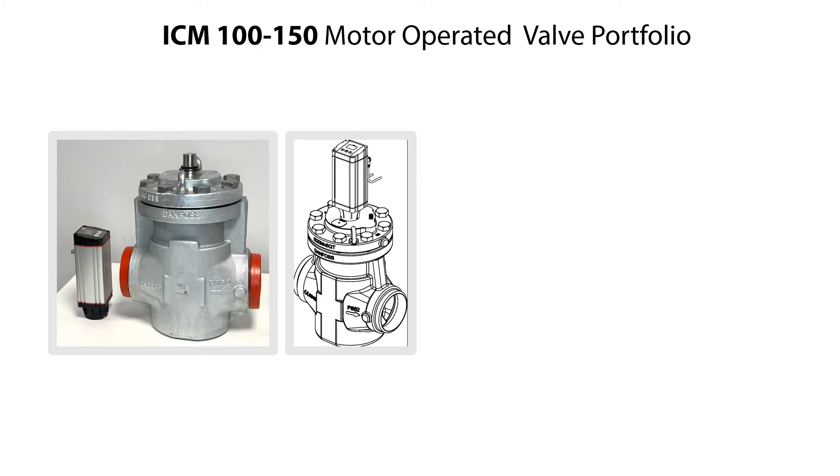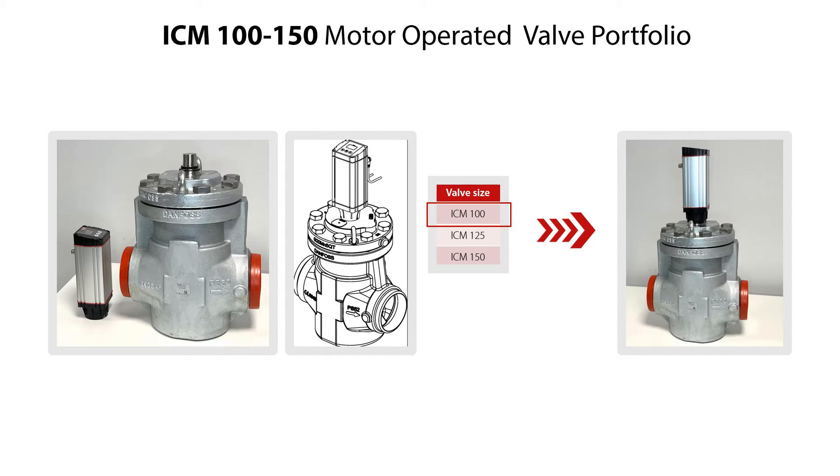The complete ICM 100-150 motor operated valves consist of a valve body with function module and ICAD actuator as seen here. This valve range includes valve sizes 100, 125, and 150, and the valves come with various types of connections. In this video we demonstrate the service of the ICM 100 valve, but the service procedure is the same for all valve sizes and variants. The service of the valve is done with the valve located on a table, but the procedures of valve disassembly, parts replacement, and reassembly are the same for a valve located in a refrigeration system.